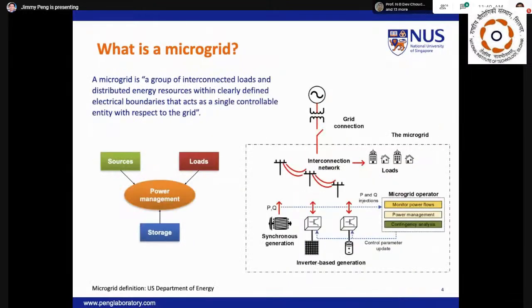Now, what is a microgrid? The US Department of Energy defines a microgrid as a group of interconnected loads and distributed energy resources within clearly defined electrical boundaries that acts as a single controllable entity with respect to the grid. Well, things are relatively simple when a microgrid is connected to the main grid. Any power imbalances can be sourced or sunk from the utility grid, thus eliminating the stability issues associated with power sharing. On the other hand, when a microgrid is operating in islanded or autonomous mode, it needs to manage all the dynamics triggered by the imbalance itself.